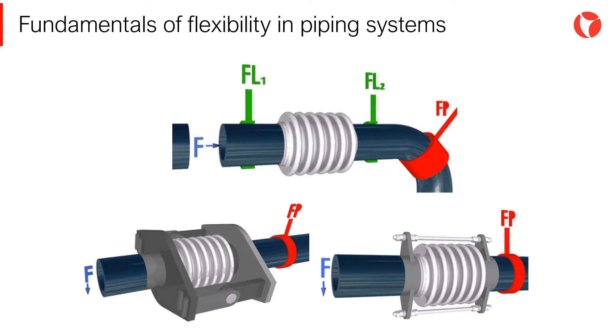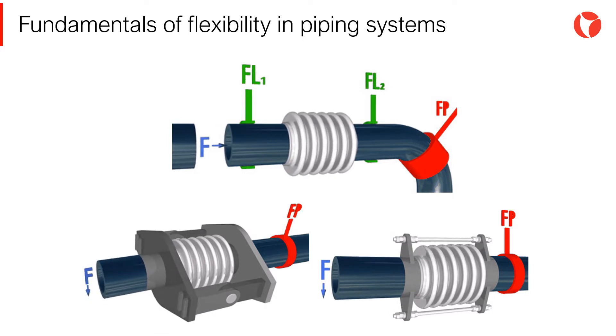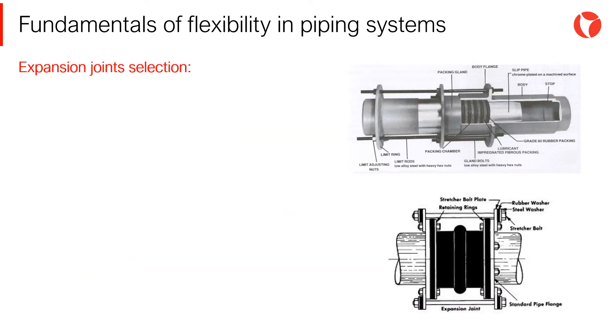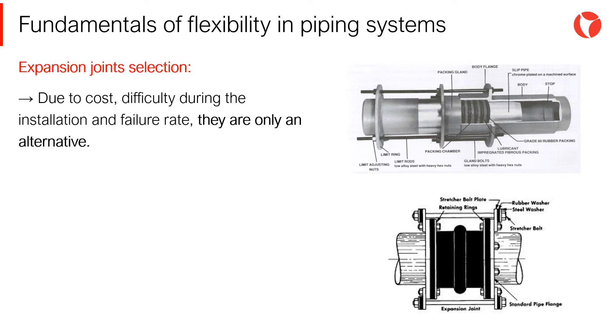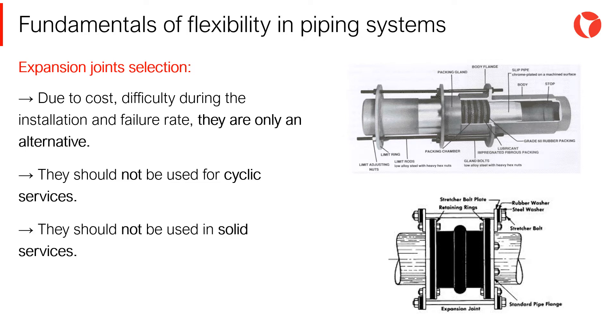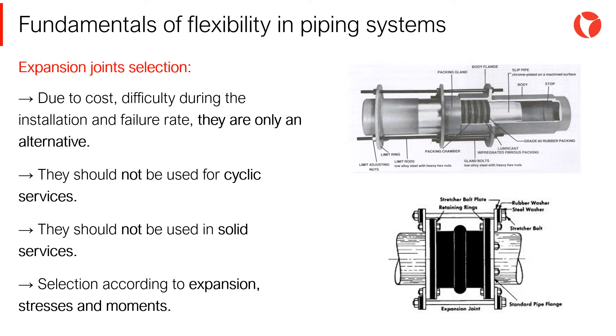Expansion joints have several moving parts and their main advantage over expansion loops is the reduced installation space required. Due to the high cost, difficulty in handling and installation, and high probability of failure, expansion joints should be used as the last resort to add flexibility to a system. Likewise, the use of expansion joints is not recommended in severe cyclic conditions, or in services which can solidify such as liquid sulfur, very heavy crude, etc. Finally, the selection of expansion joints is made according to the expansion, stresses and movements in the line.